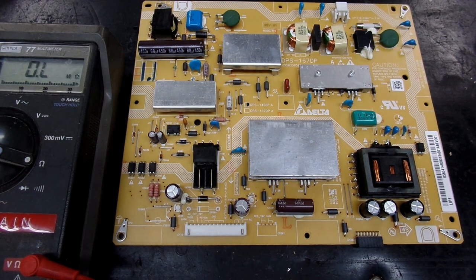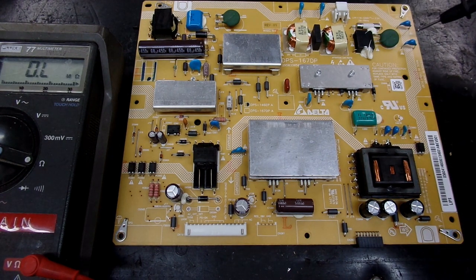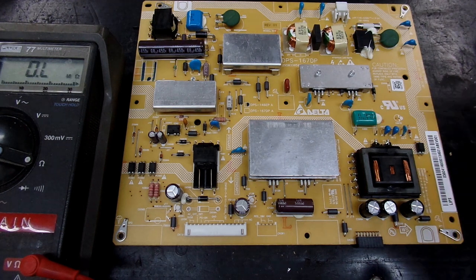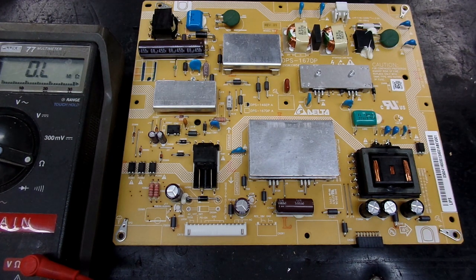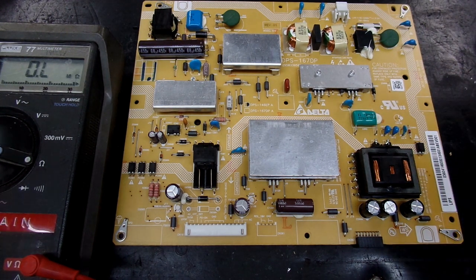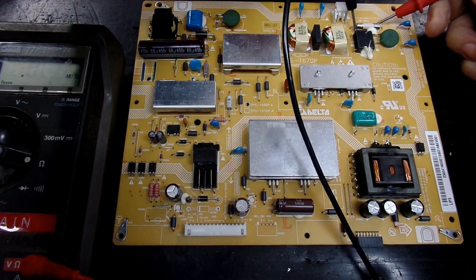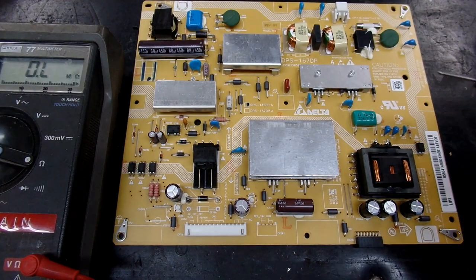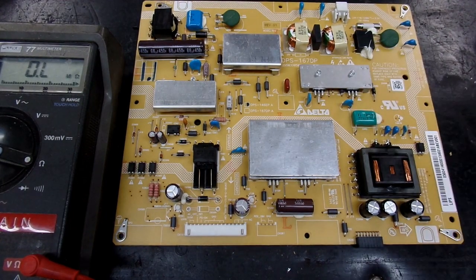The first thing I did when I got the board is check to make sure that the fuses and the surge suppressors are okay, and they all look good. The fuse is good. If you look at my meter here, I have it on ohms. The fuse reads 0 ohms. As well, I checked all of the FETs and the power transistors and the SCRs, and everything there looks good.